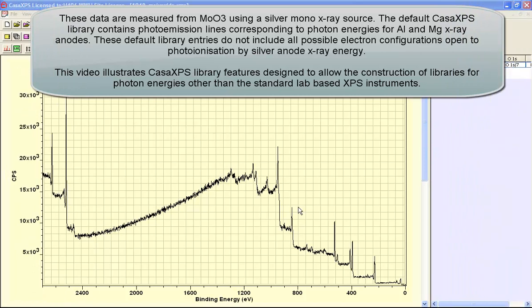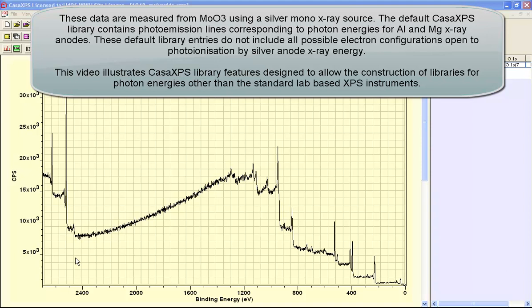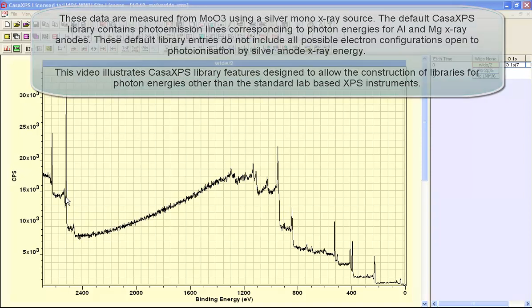XPS is performed by irradiating a sample with X-rays of a specific energy. The most common X-ray used for XPS lab-based systems is aluminium. However, not all instruments are limited to aluminium and this spectrum is an example of a silver anode X-ray source which has produced X-rays twice the energy of the standard aluminium anode X-ray gun and as a result we are able to see core levels that are not available to the aluminium X-ray based systems.